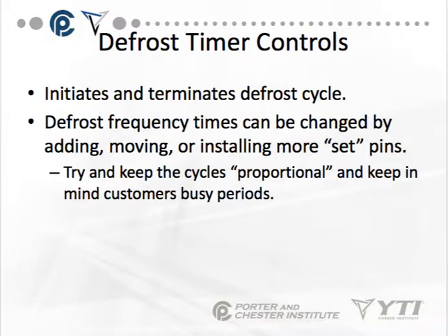So the defrost timer control, which is the defrost clock, initiates and terminates the defrost cycle. The defrost frequency times can be changed by adding, moving, or installing more set pins. Those are the pins on the outer dial if you think back to one of our last videos.